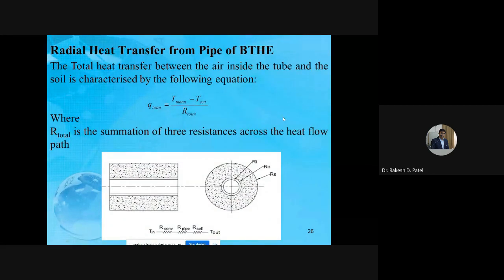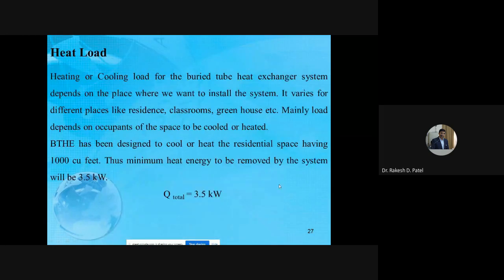Now the total heat transfer between the air inside the tube and the soil is given by the following equation: Q equals the mean tube temperature minus the outer temperature, divided by the resistance. R total is the summation of three resistances across the heat flow path. The figure shows what R total is, the resistance of three components.